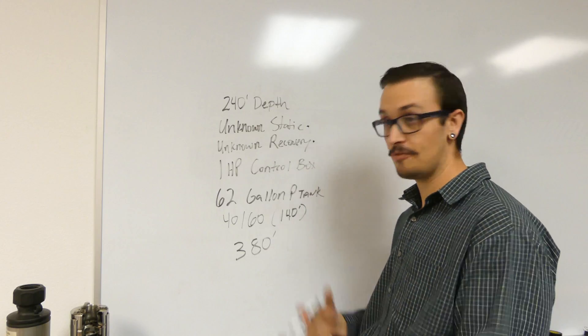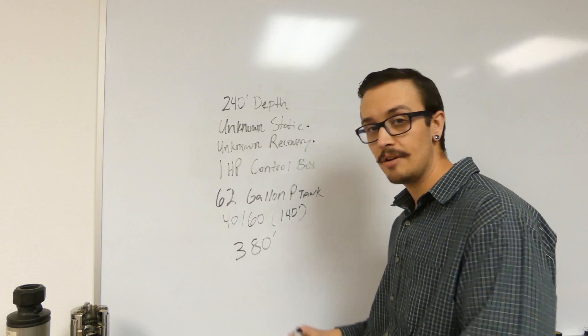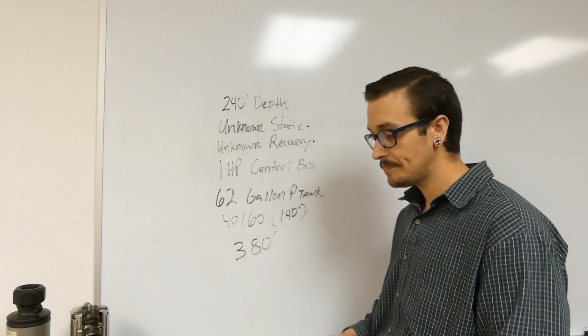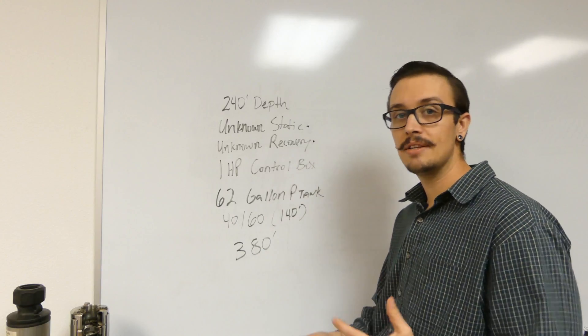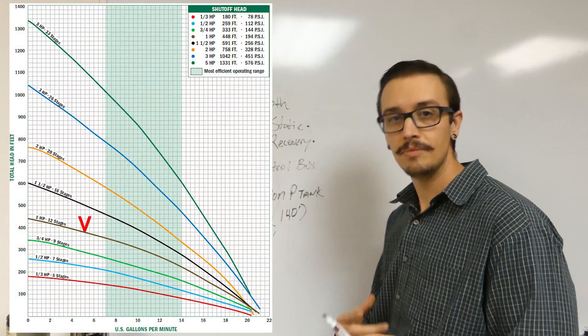We know it's one horsepower, so you might be surprised to know that we can actually figure it out from here. Since we know it's one horsepower and 380 feet TDH, we look at some pump curves and we find that the 10 gallon a minute - we're just starting in the middle - the 10 gallon a minute.